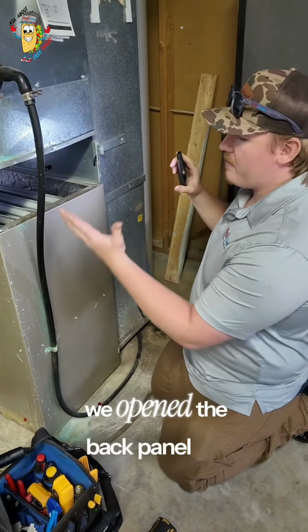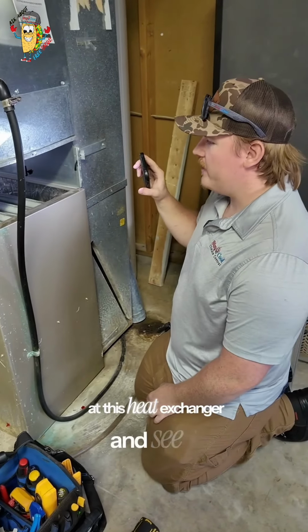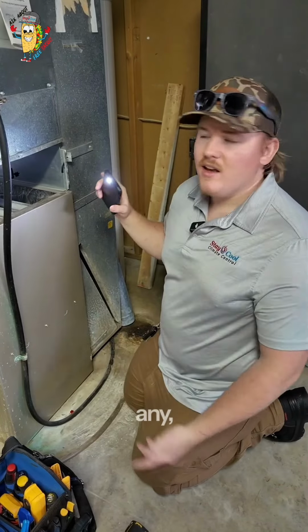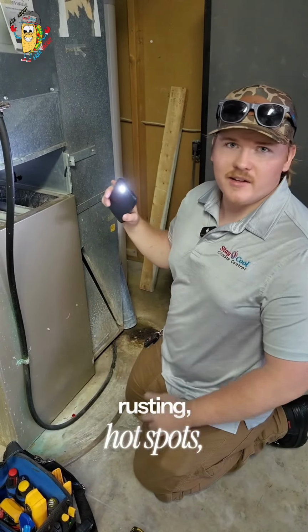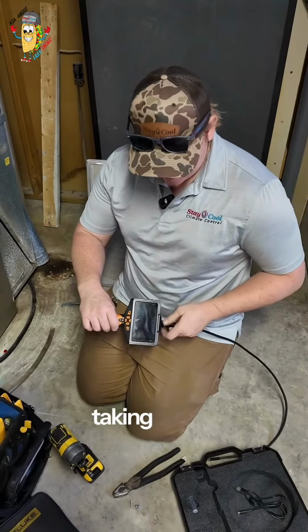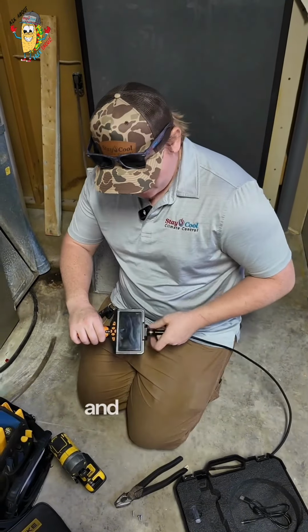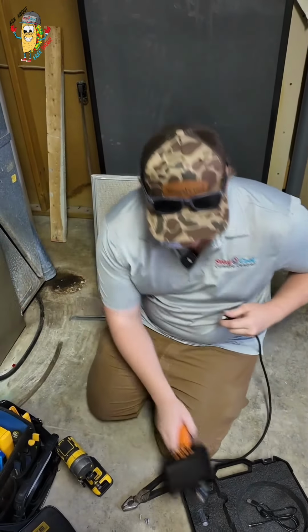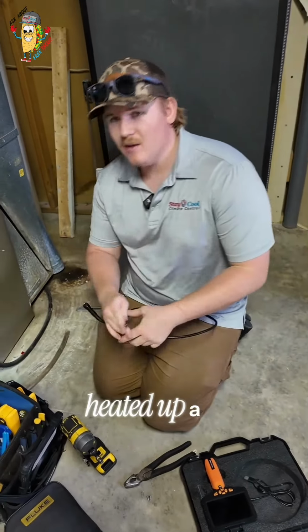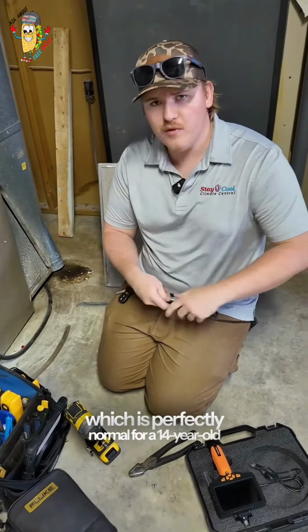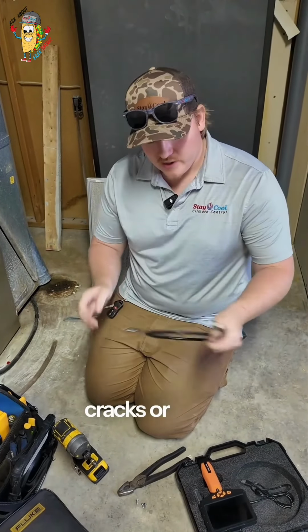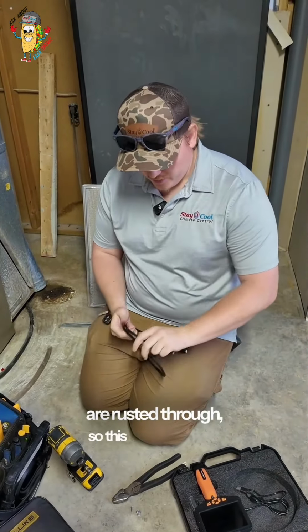So we opened the back panel up here, and we're going to take a look at this heat exchanger and see if it's got any cracks, any rusting, hot spots, see if there's any problems with it. So we got done taking a look at the heat exchanger, and it does have some hot spots on it, just sections of the metal where it's heated up a lot over time, which is perfectly normal for a 14-year-old furnace. Didn't find any cracks or holes or spots that are rusted through, so this heat exchanger looks safe.